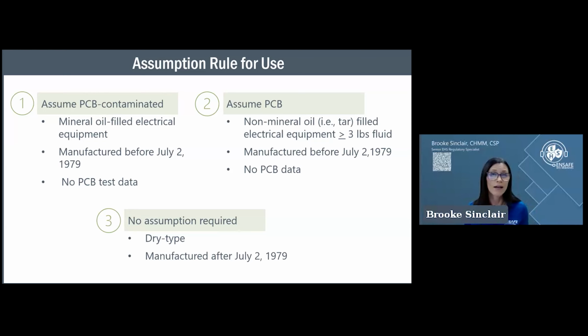Most utilities did not proactively sample unless planning removals. There were issues where transformers were tapped for sampling and shavings fell in, causing failures afterward. So many utilities decided not to tap the transformer, instead going with the assumption rule and working through replacement as part of normal asset management.